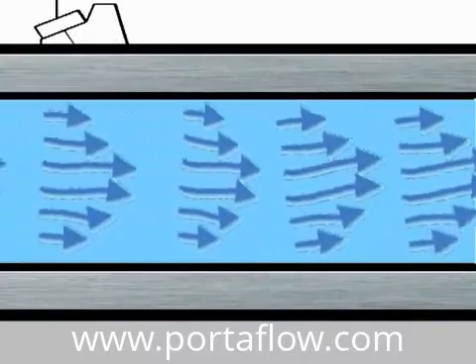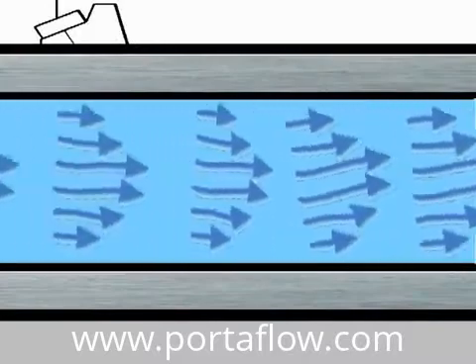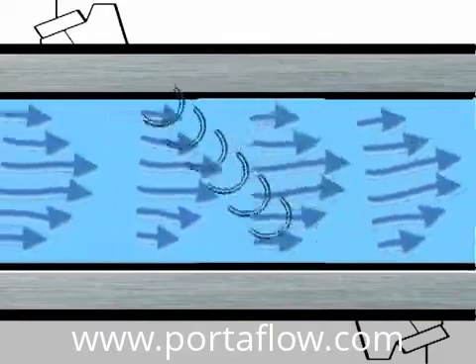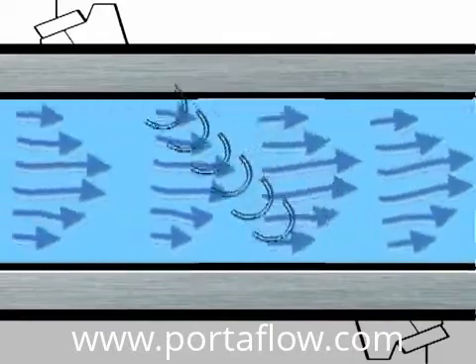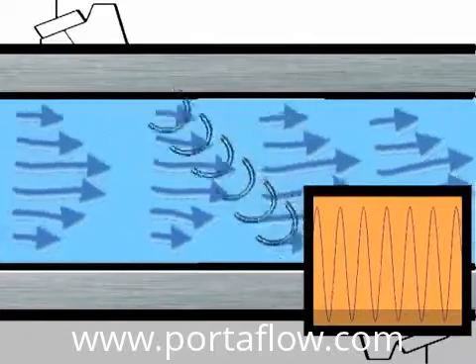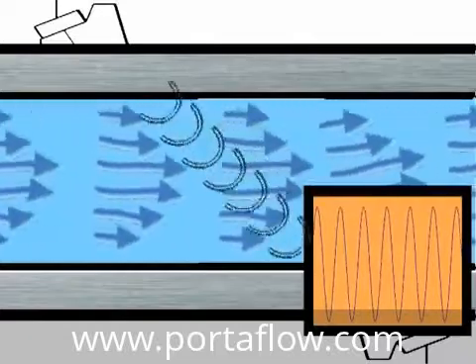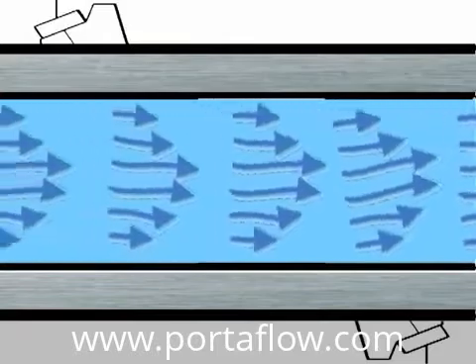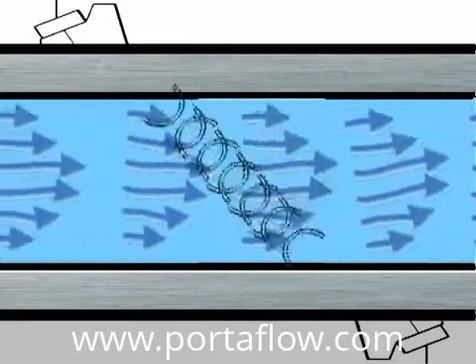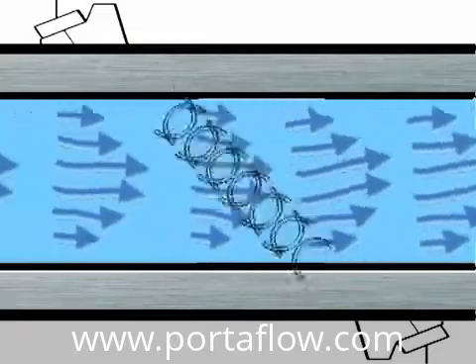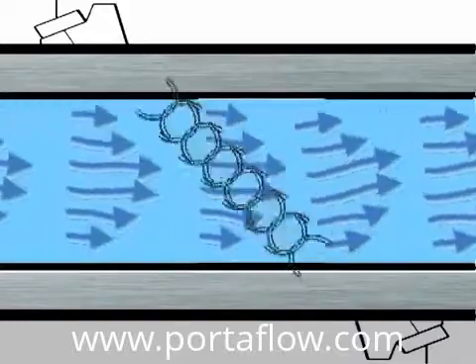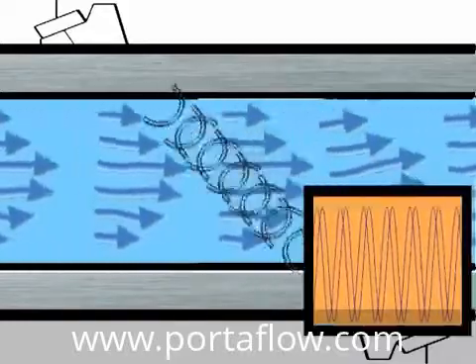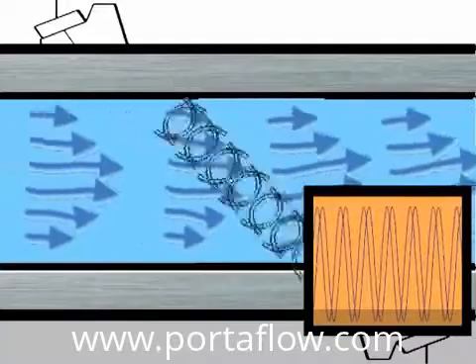Ultrasonic signals are highly directional. Providing the pipe material and the fluid in the pipe conducts ultrasonic signals, an ultrasonic signal transmitted across the pipe can be received on the other side. When signals are sent simultaneously from both sides, the signal travelling with the flow will arrive faster than the signal travelling against the flow.